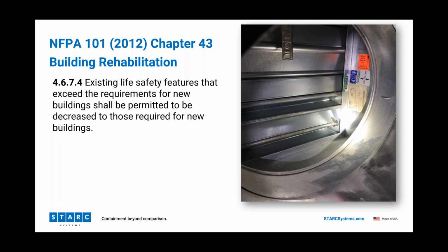Existing, so this is where we tie back to Chapter 4, and I am going to read this exactly: existing life safety features that exceed the requirements for new buildings shall be permitted to be decreased to those required by new buildings. It's exactly what we just talked about. You can take existing features that exceed and bring them to the new building requirements. An example of this real quickly is corridors. Prior to 1991, corridors in healthcare had to be 1-hour rated. After that, they only had to resist the passage of smoke. If you haven't modified that building or changed the life safety drawings, you are permitted to do that so long as you are protected throughout with automatic sprinkler systems in accordance with NFPA 13.